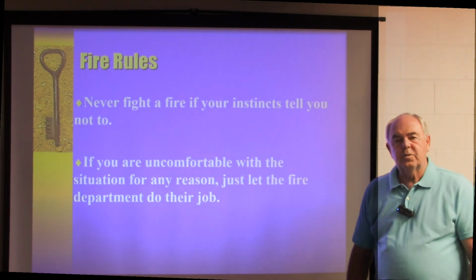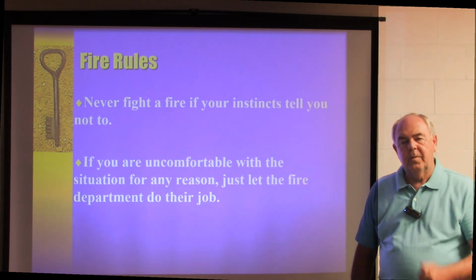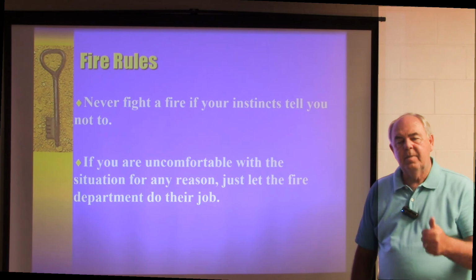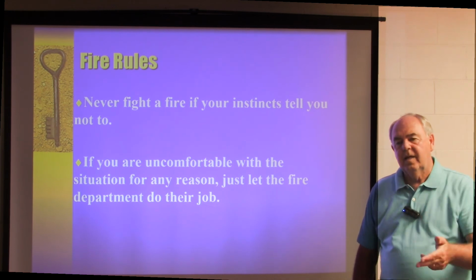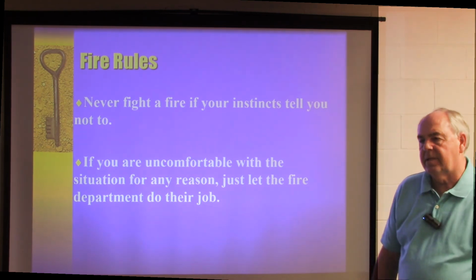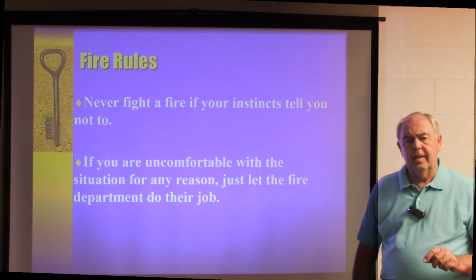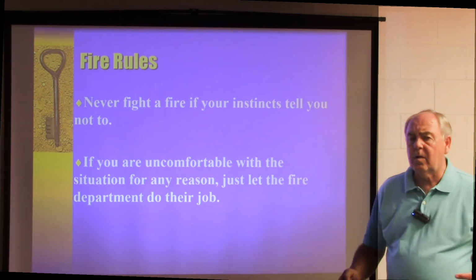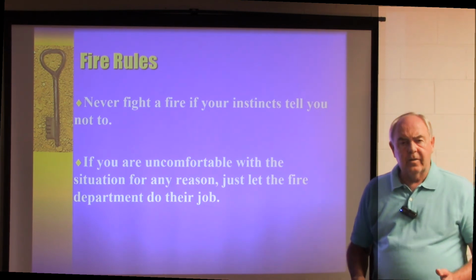That's fire extinguisher training. Remember, pull, aim, squeeze, and sweep. And remember, the classes of fire are A, B, C, and D. A is wood, paper, plastic; B is fuel, oils, and grease; C is the electrical type fires; and D, the metal type fires. Always make sure you're familiar, in your shop or in the area that you work, whatever manufacturing plant, with the location of your fire extinguishers.